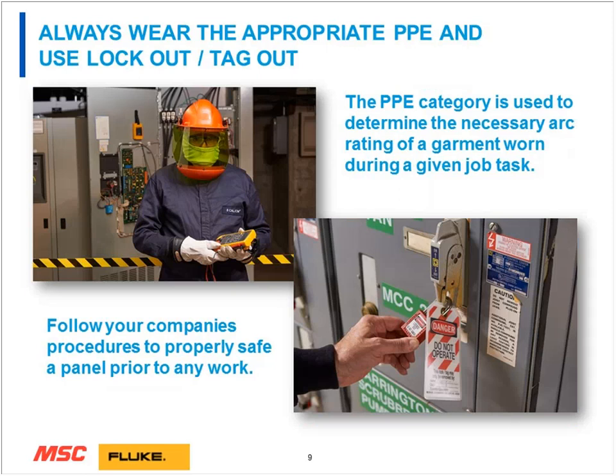Always wear the appropriate PPE and use lockout tagout. And what does that mean? Well, the appropriate PPE can vary depending upon the electrical environment that you find yourself in. In some cases, at a minimum, it should be the protective gloves, eyewear, hearing protection, the leather shoes, perhaps other types of safety gear, all the way up to wearing a balaclava with the face shield, flame-resistant clothing at different therms, at different levels, and also following the correct procedures. So many companies deal with a lockout-tagout procedure where you're safing that panel, but you do have to be aware of any dual feeds that can possibly happen. So just be aware of that.